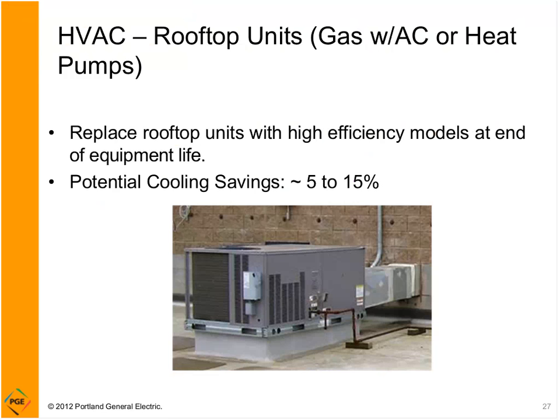So these units typically have a somewhat limited life. You might expect maybe 20 years out of them. When you're faced with major repairs, it's a good idea to look at the high efficiency options. Don't maybe just look at the cheaper option that's standard or federal minimum. Look at the high efficiency options and, again, incentives for this type of upgrade. Generally, it doesn't make sense or pencil out to replace these for efficiency's sake alone. But at the time of replacement, it can be and should be something that's looked at. So, potential cooling savings, looking at a code unit versus a high efficiency unit, are 5 to 15%. So worth looking at.